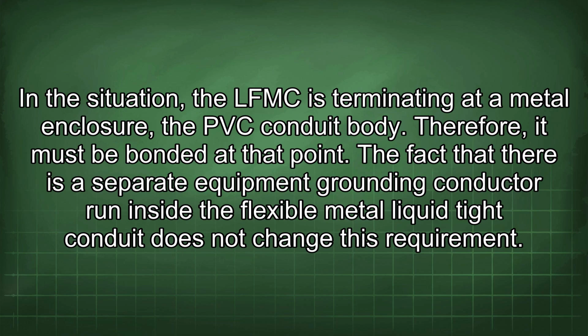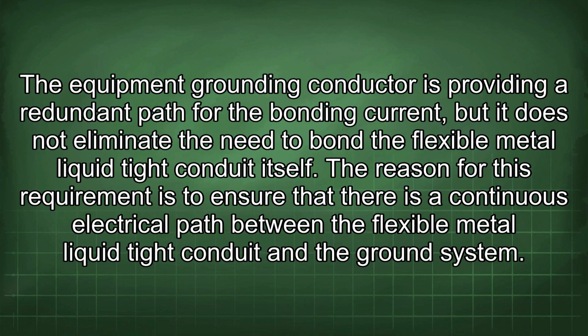The fact that there is a separate equipment grounding conductor run inside the flexible metal liquid tight conduit does not change this requirement. The equipment grounding conductor is providing a redundant path for the bonding current, but it does not eliminate the need to bond the flexible metal liquid tight conduit itself.